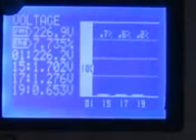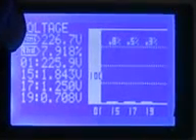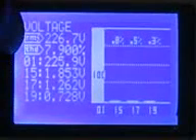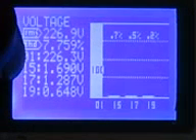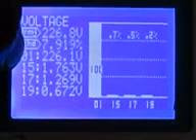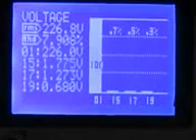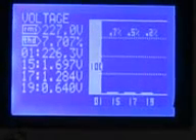After pressing next page, you can see the voltage harmonics. Here is the RMS value of voltage. This is the total THD percentage, 7.79%, and these are the harmonics. 0, 1 is the fundamental harmonic, and these are the 15th, 17th, 19th. You can view more harmonics by pressing the up or down button.